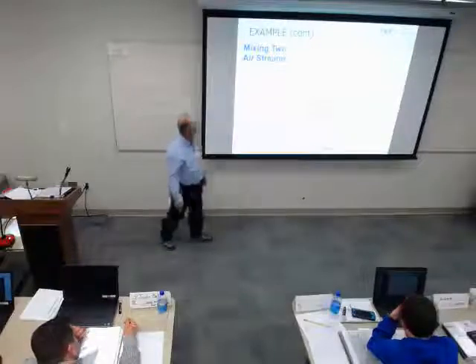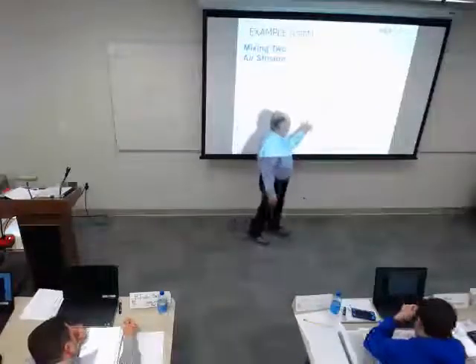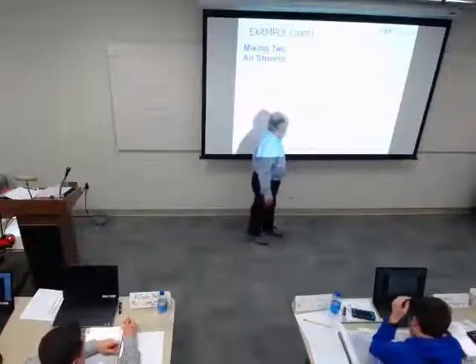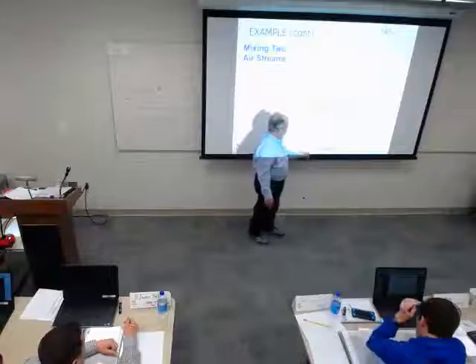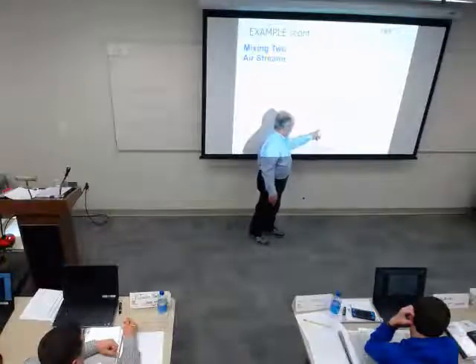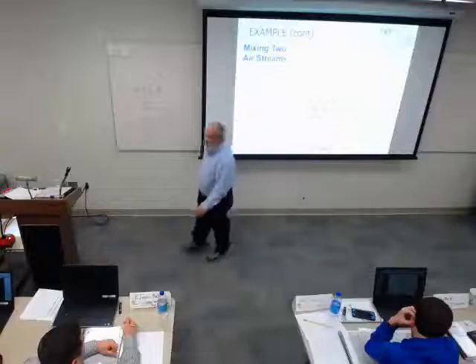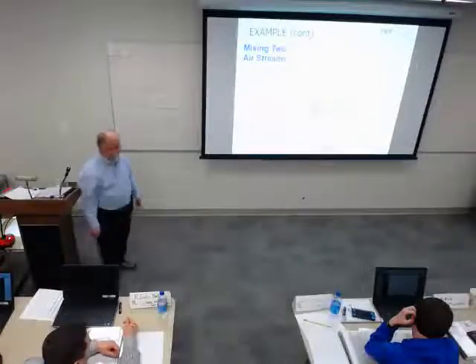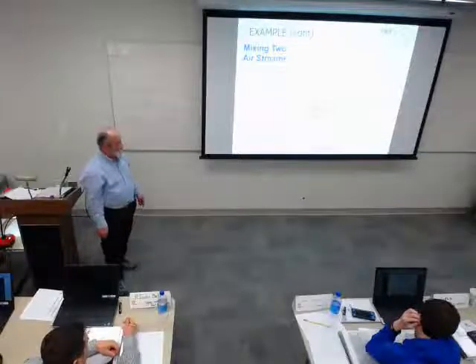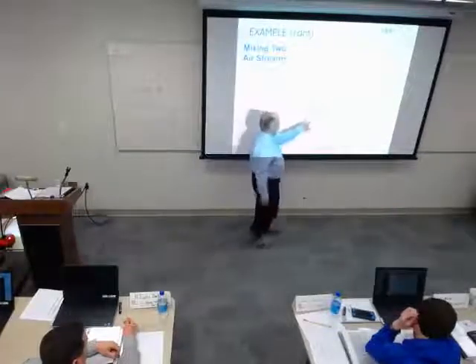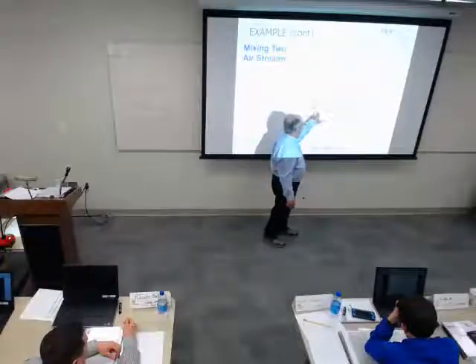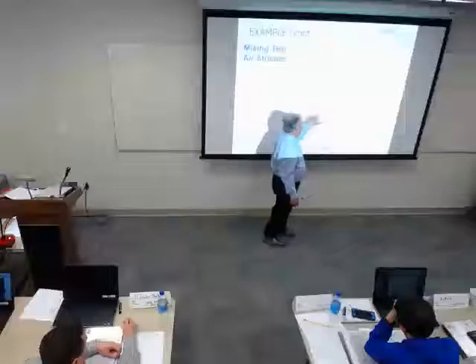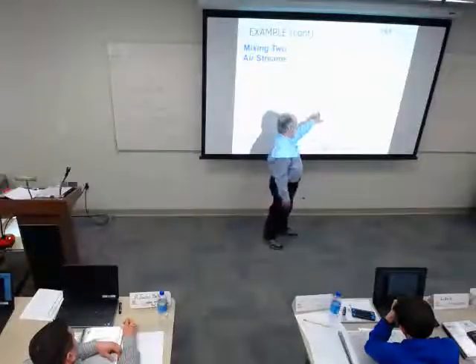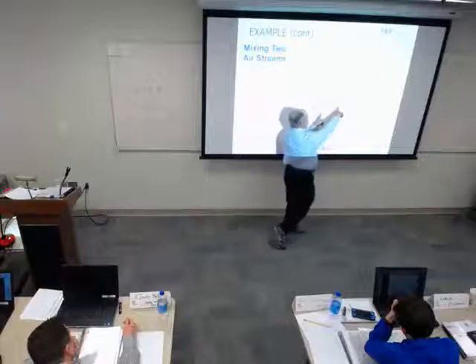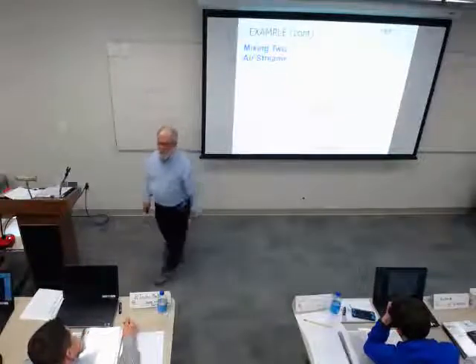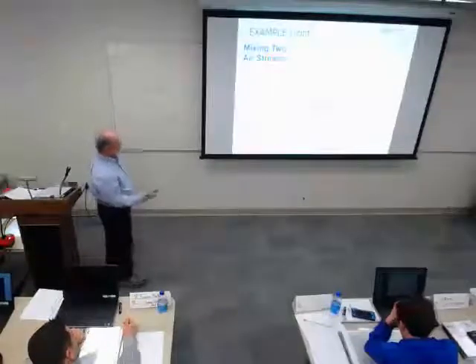So they did the count that we just did. What you can do is you draw a line there, draw a line there, and then you know what your mixed air temperature in Fahrenheit is. And you come up there, and before you intersect that line is the point that you are between those two. And that also tells you your relative amounts of air. This right here, it's kind of inverse. This tells you that's that much of outside air, that much of return air. That's kind of counterintuitive until you write the formula out a couple times. You go, oh, I see it. But right now, it's just good to know.